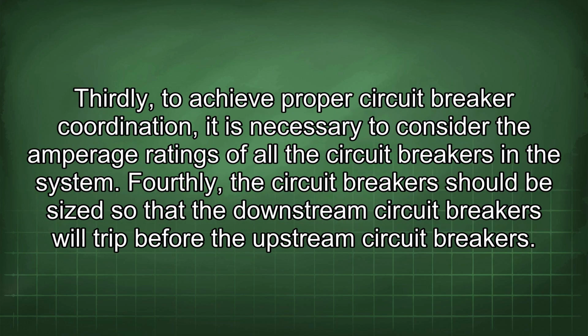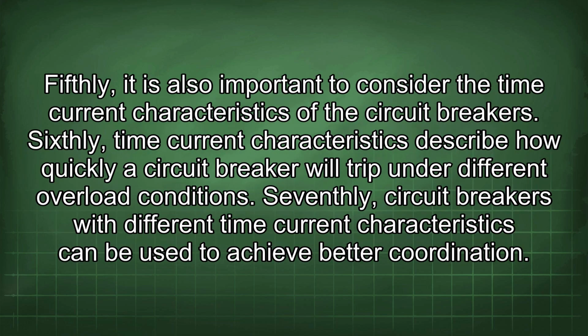Secondly, proper circuit breaker coordination can help to prevent nuisance tripping and to minimize the impact of a fault. Thirdly, to achieve proper circuit breaker coordination, it is necessary to consider the amperage ratings of all the circuit breakers in the system. Fourthly, the circuit breaker should be sized so that the downstream circuit breakers will trip before the upstream circuit breakers. Fifthly, it is also important to consider the time current characteristics of the circuit breakers. Sixthly, time current characteristics describe how quickly a circuit breaker will trip under different overload conditions. Seventhly, circuit breakers with different time current characteristics can be used to achieve better coordination.